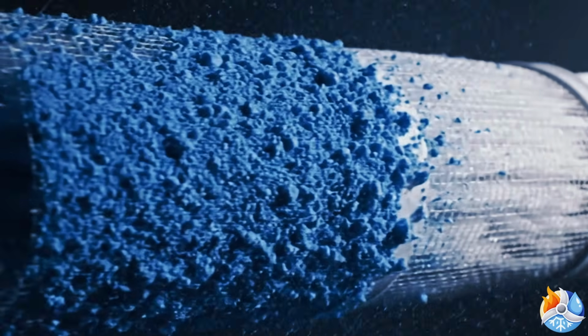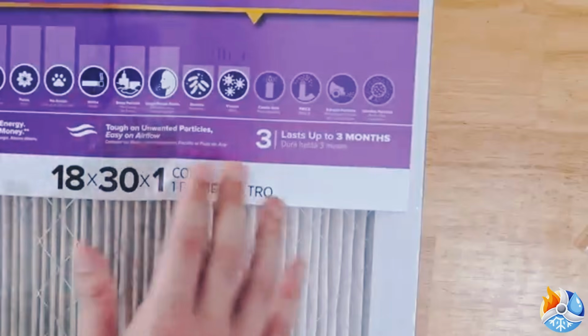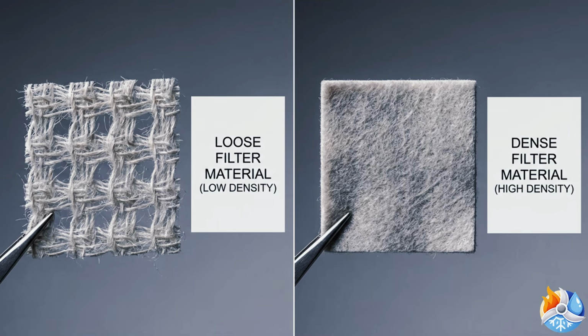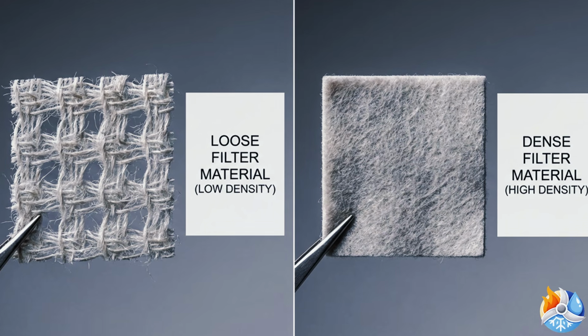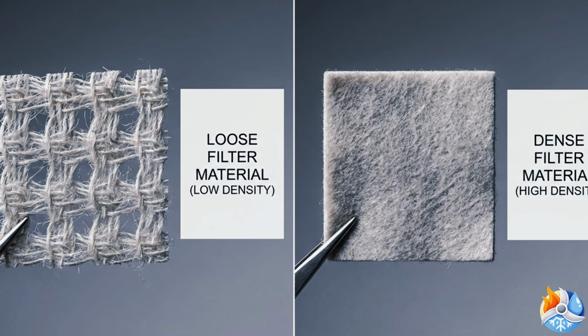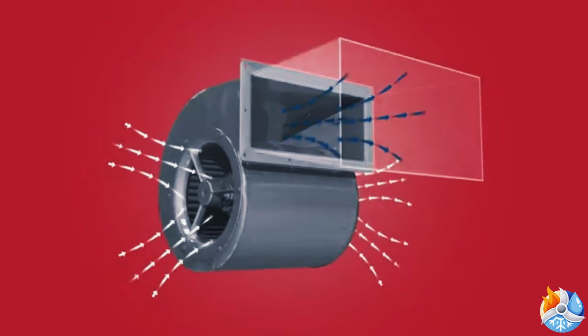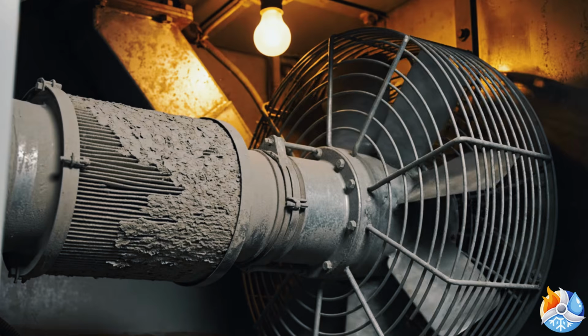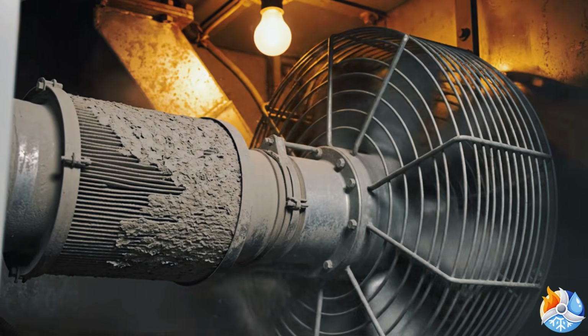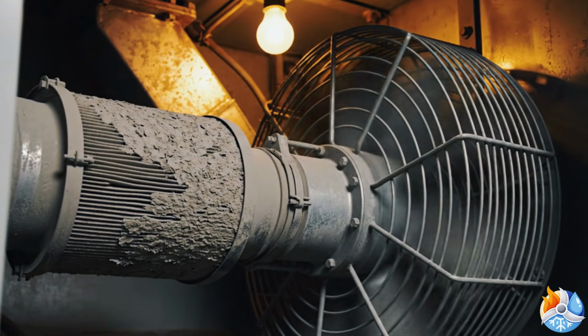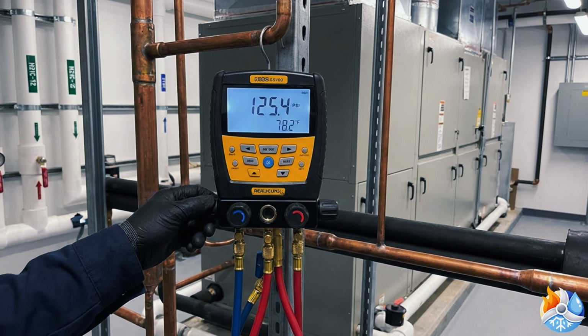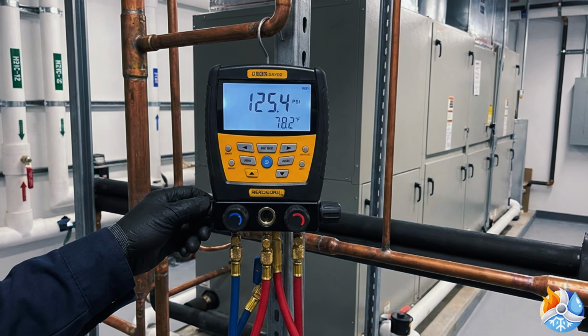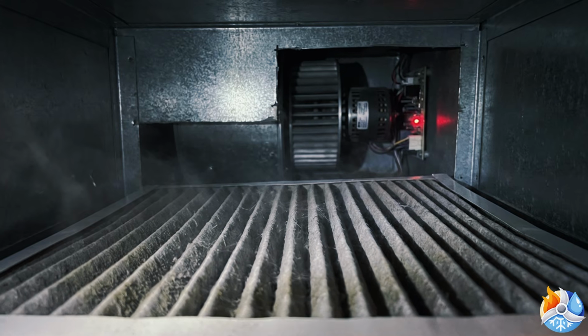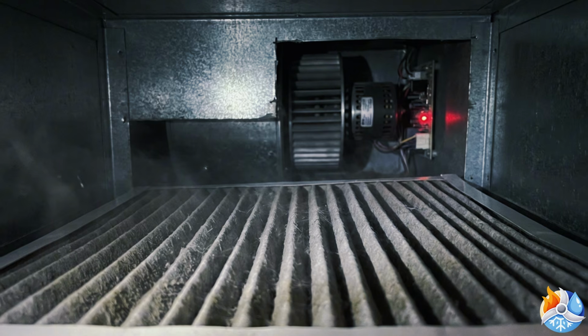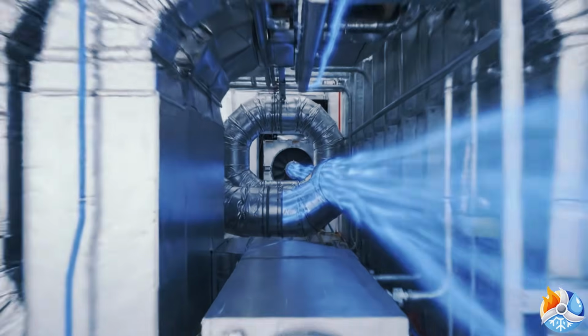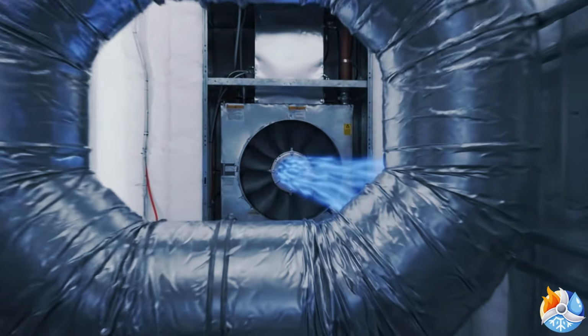More filtration is better. Obvious choice, except here's the physics that no one on the packaging mentions. To catch smaller particles, the filter material has to be denser. Denser material means less space for air to pass through. Less space means more resistance. More resistance means your blower motor has to work significantly harder to pull the same volume of air. Engineers call this pressure drop. And every heating and cooling system has a design limit for it. Push past that limit, and most residential systems will exceed it with a top-tier 1-inch filter, and you start doing real damage. Your system was designed to move a specific amount of air per minute.